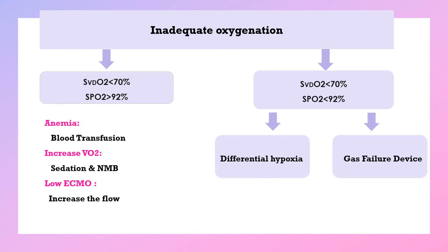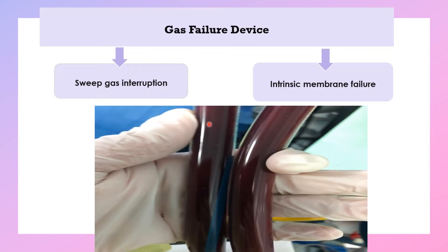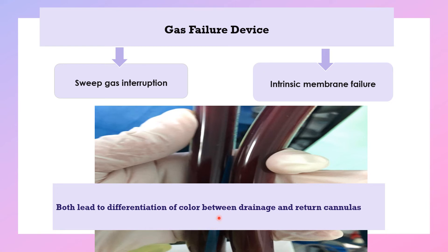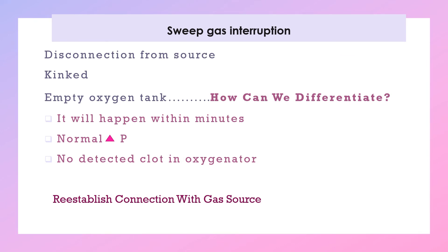Moving to another cause of inadequate oxygenation: gas failure device or oxygenator failure. This can be caused by sweep gas interruption or intrinsic membrane failure, both of which lead to loss of color differentiation between the drainage and return cannulas. Sweep gas interruption is a very important cause of hypoxemia or hypercapnia. Causes include disconnection from the source, kinking in the tubing, or an empty oxygen tank. It occurs within minutes, with normal delta P (P2 minus P1) and no clots detected in the oxygenator. The solution is to re-establish connection with the gas source.